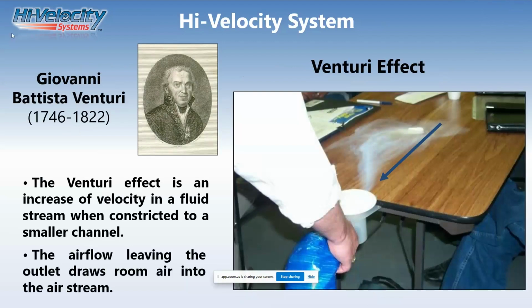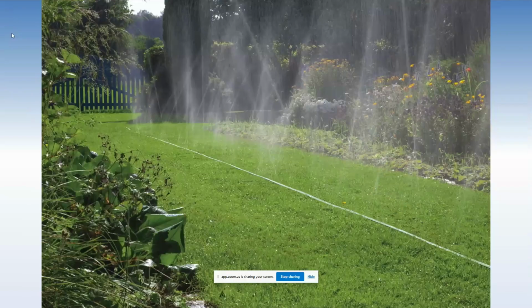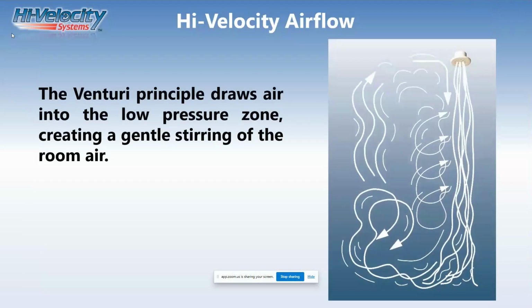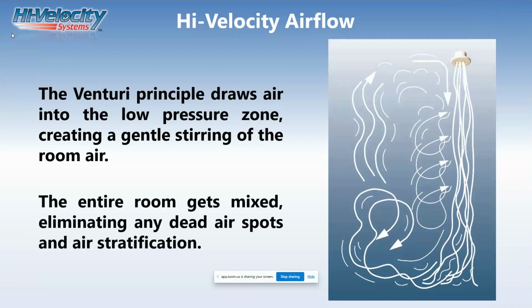So in a Venturi action, it's taking the rest of the air in that room and stirring up the room side to side, top to bottom. It's like a sprinkler hose or a soaker hose. You connect that hose to the tap, and it doesn't matter if it's the first outlet or the last outlet, it's the same amount of volume coming out of it. Well, that's high velocity. Now, the Venturi principle draws air into a low pressure zone, creating gentle stirring of the room air, and the entire room gets mixed, eliminating dead air spots and air stratification.